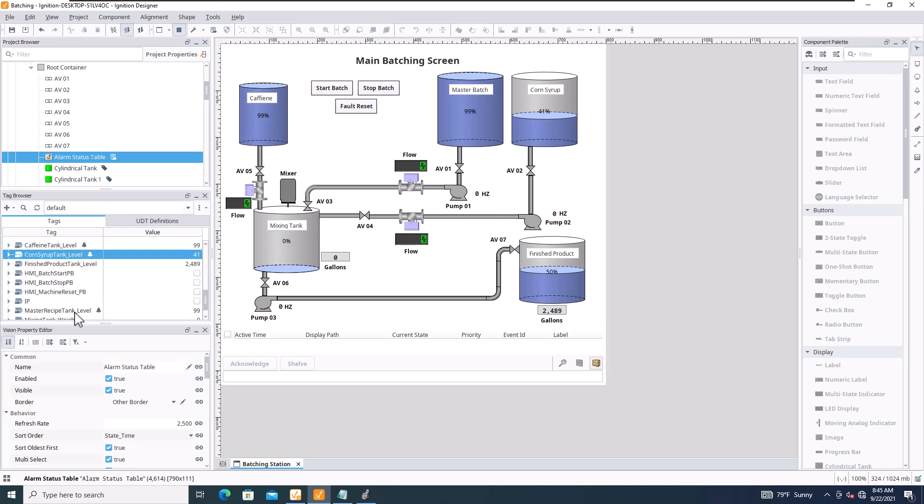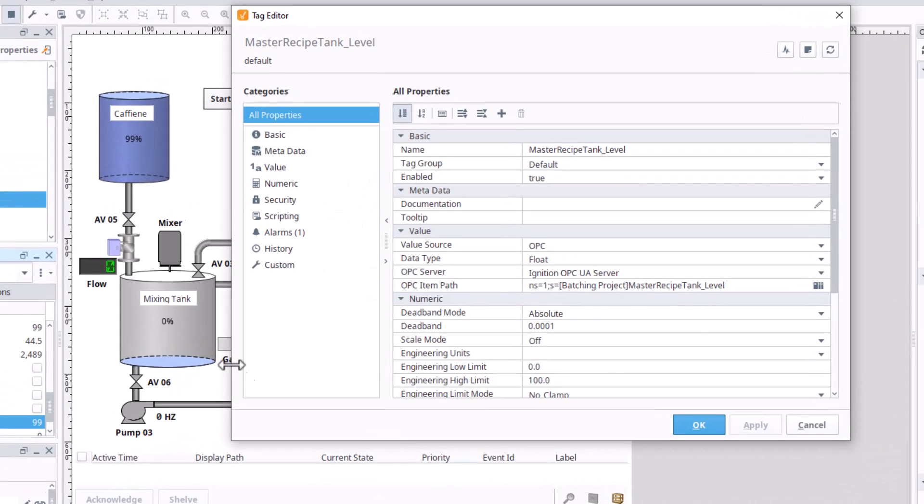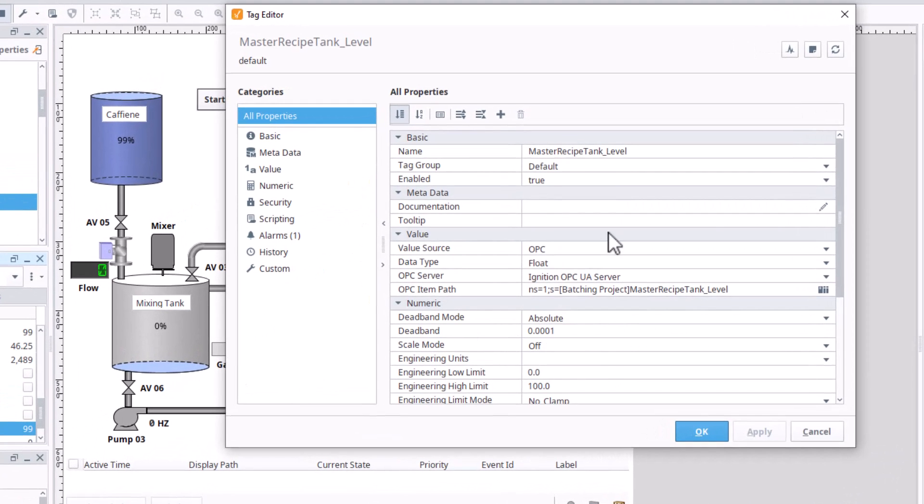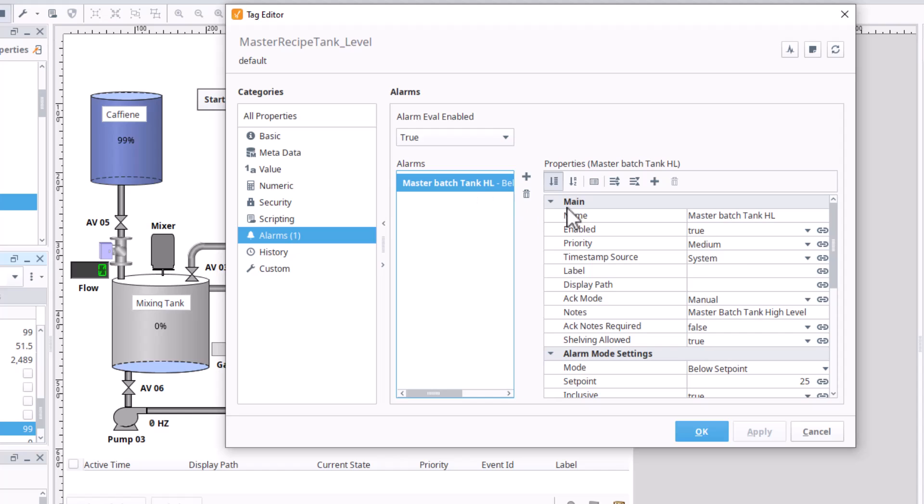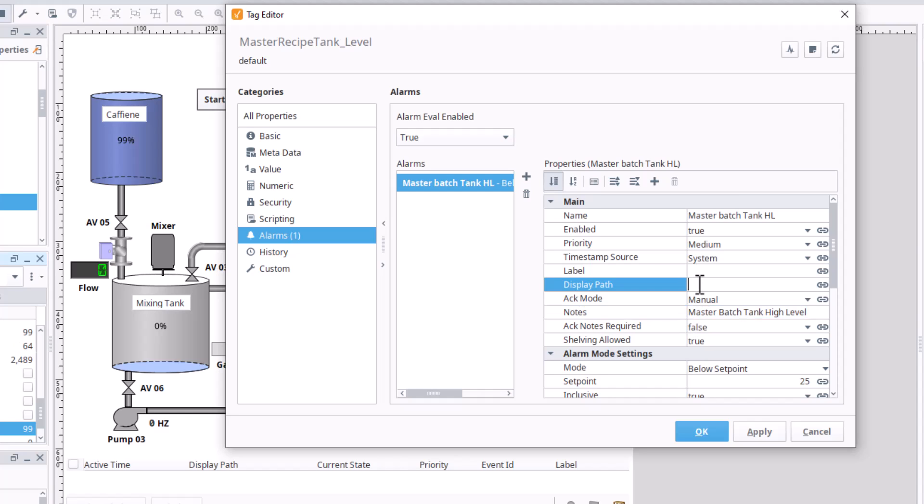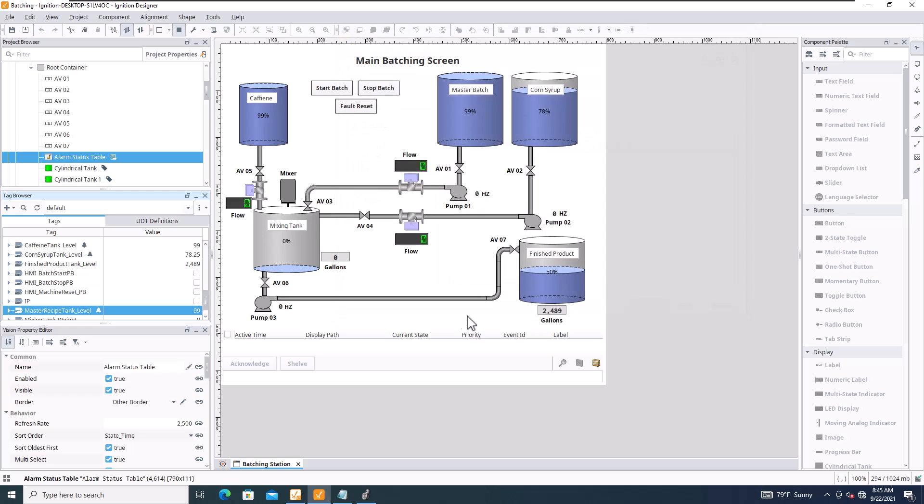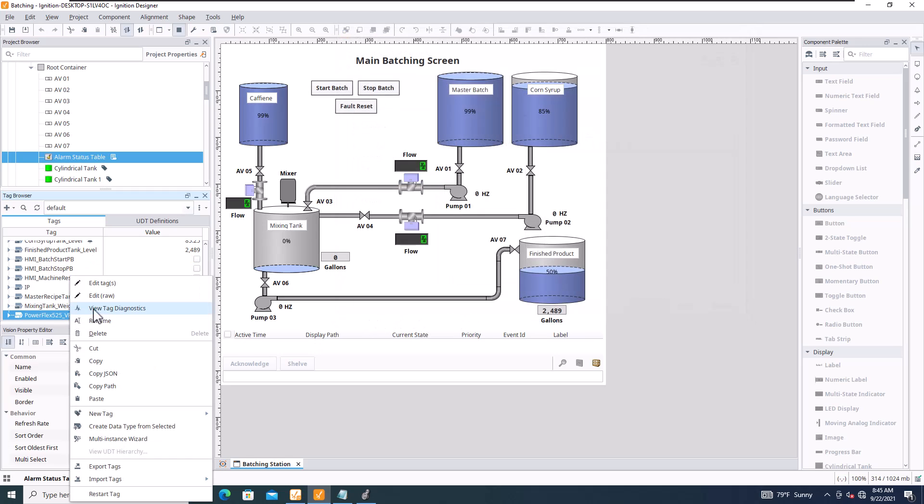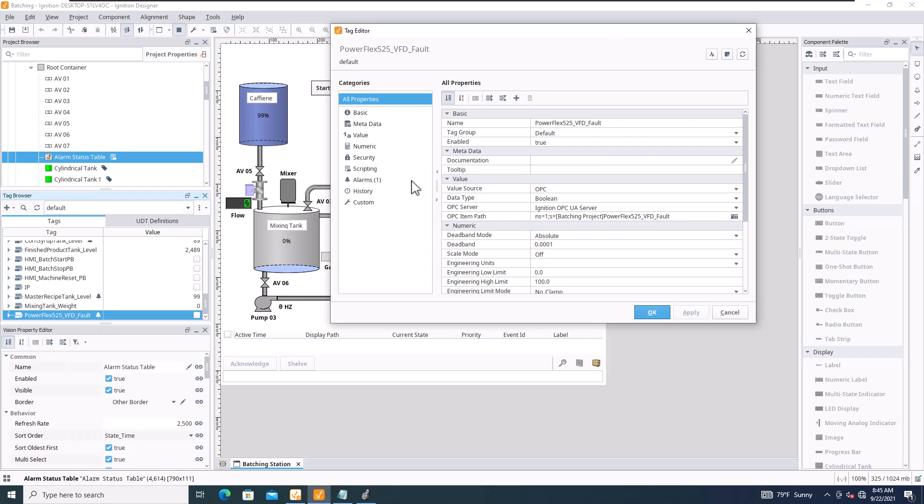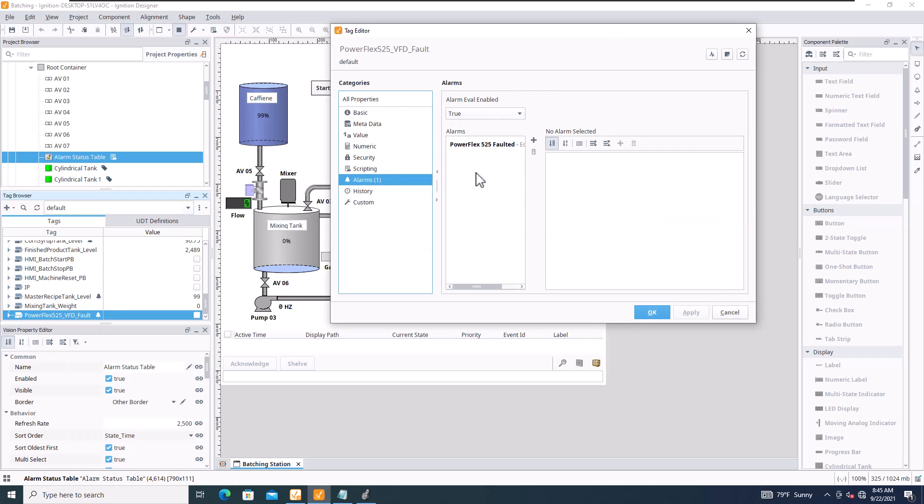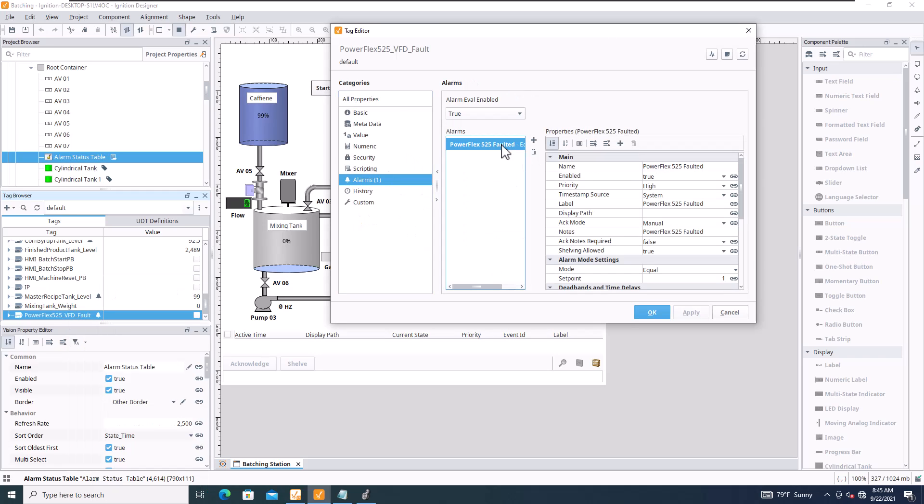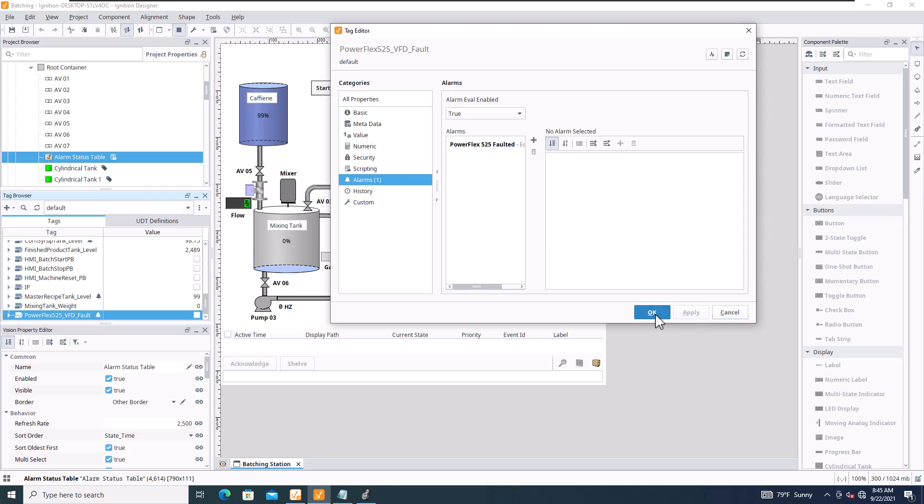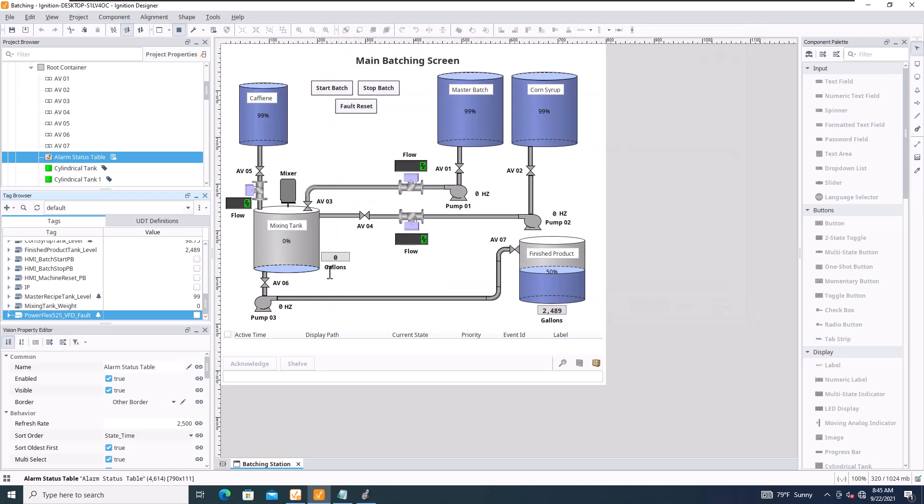So we need to do that to all of our alarms. We'll come over here to this next set and then come over here to alarms. And again when we talked about the notes, the notes I feel like is a good display path and you can put this, have some kind of text or something with a tag if you want but I'm just hard coding it. And then we'll have VFD fault as well because those are the alarms we've put in so far. So for label you can see this is VFD fault path and we're gonna call that power flex fault.